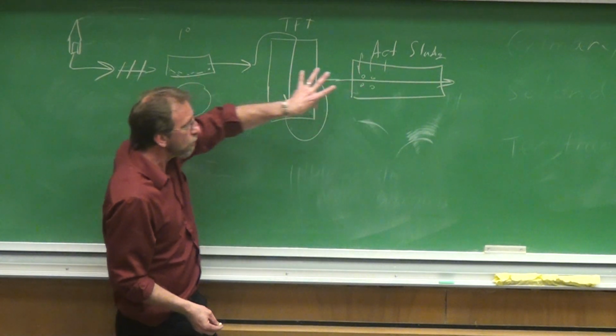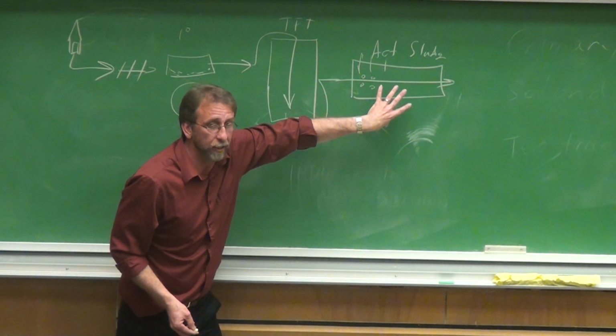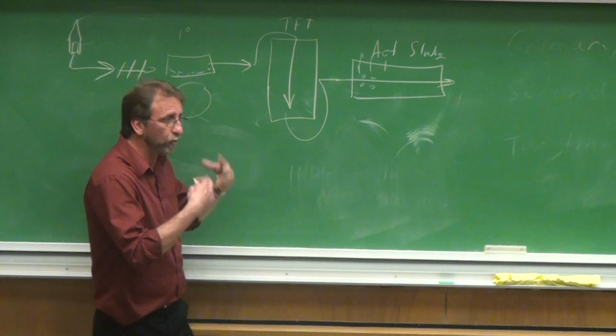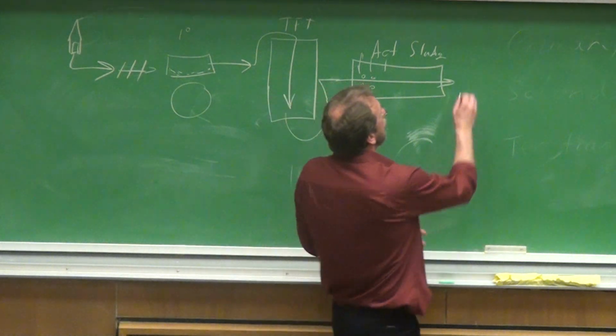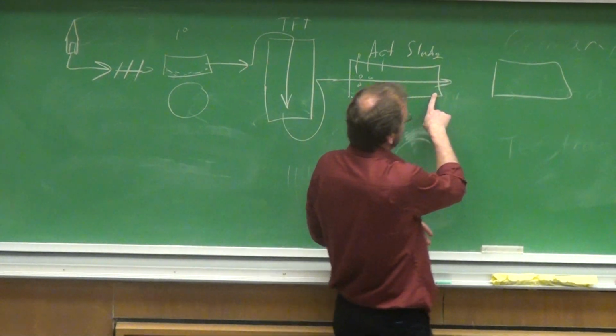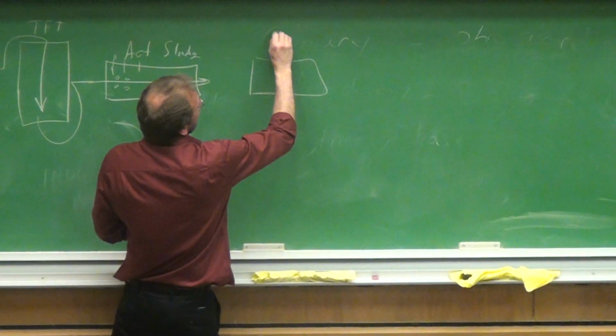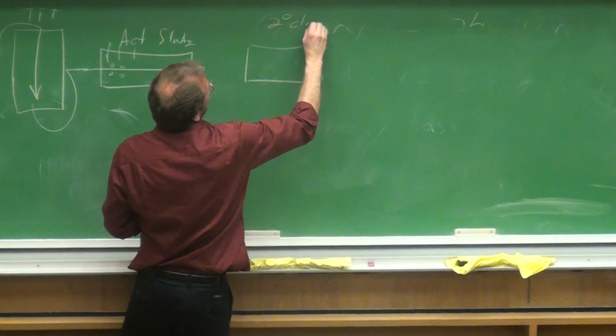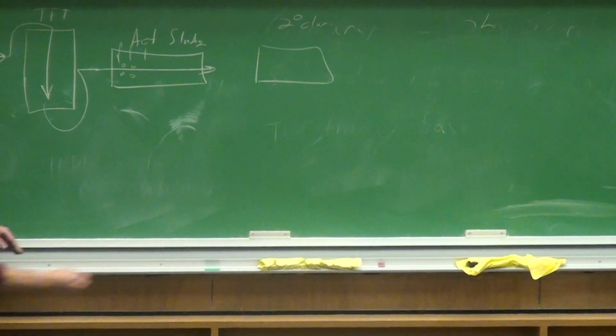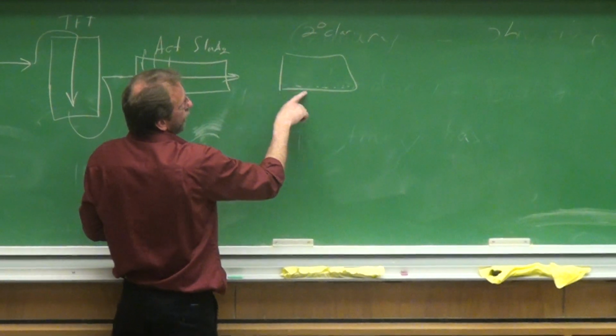These are the two largest BOD reducing processes in the treatment. Trickling filter tower and activated sludge, because the microbes are actually breaking down the organic matter. Now, we've got a lot of microbes still in this water that's coming out of the activated sludge. So we take it to our secondary clarifier, which is no different than our primary clarifier. It just slows the water down, lets the organisms that were there settle out.